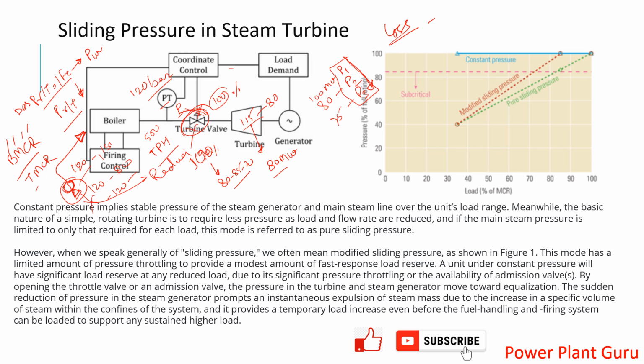my plant is running at 80 megawatt. I'm taking an example. My plant is running at 80 megawatt, and my control valve is full open, and suddenly I get a signal to increase my load to 100 megawatt. Then what do I have to do? I don't have any margin here in this sliding pressure because my valve is full open. What will I do?